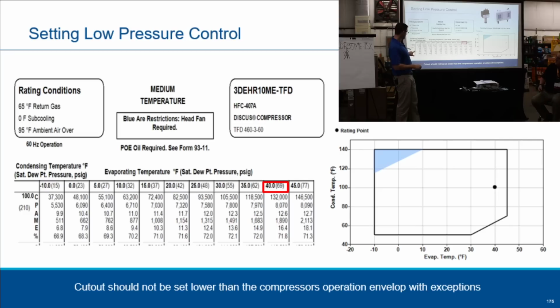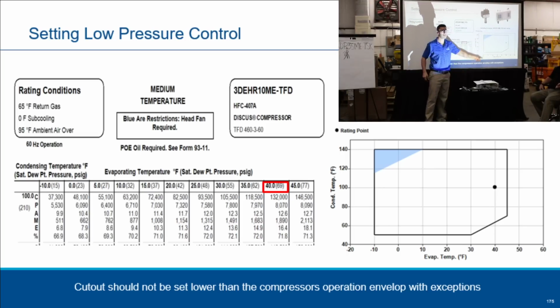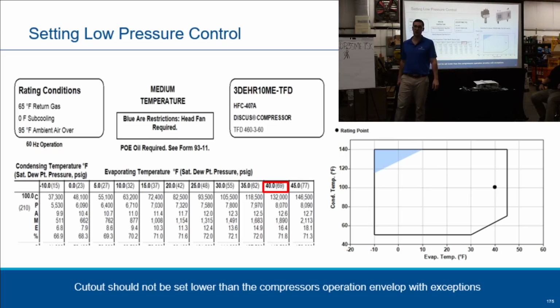At 100 condensing and 40 evaporating, which is 69 psi, running right here. This is what my design conditions are. So if it's a 10 TD on that evaporator coil, that's a 50-degree box. And this is the 40 SST, which is 69 psi. That's where it normally runs. If I set this one here to 5 psi, so right here it says 15 psi, this line right here is 15 psi, and I set it for 5 psi, what am I doing to the compressor now?